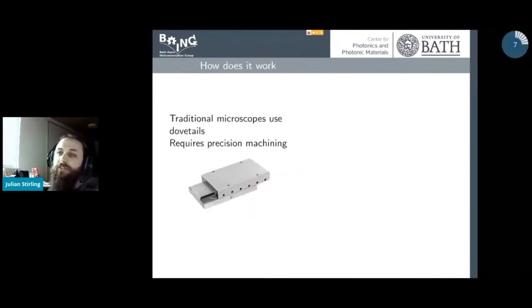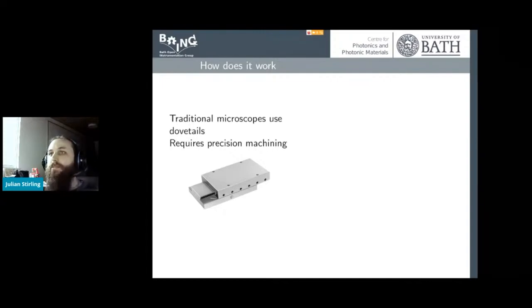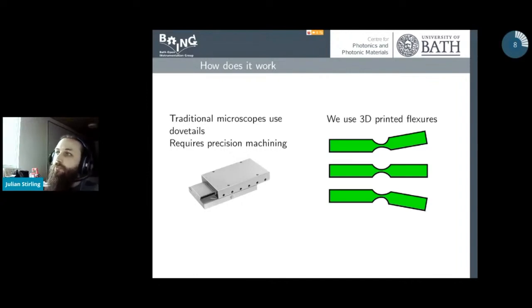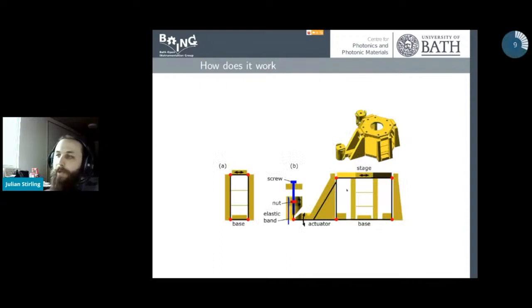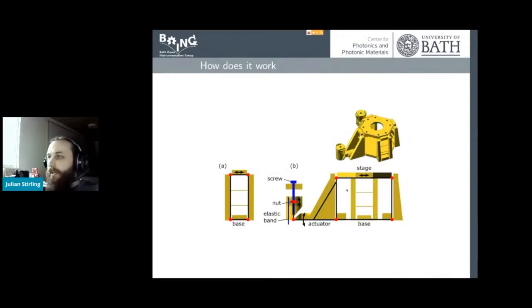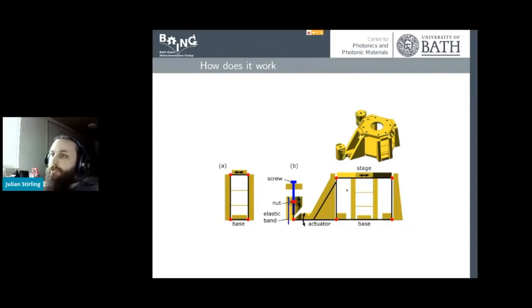A traditional microscope uses dovetails and highly machined surfaces to get very precise motion. When 3D printing, making a dovetail doesn't work well, but we can build flexures — we thin a piece of plastic and it will bend reproducibly. By putting many small flexures across a big monolithic stage, we can actually build up very fine, precise motion.